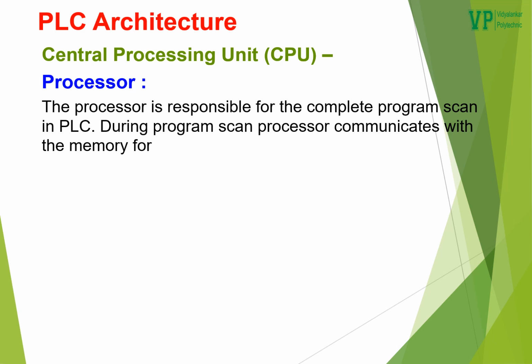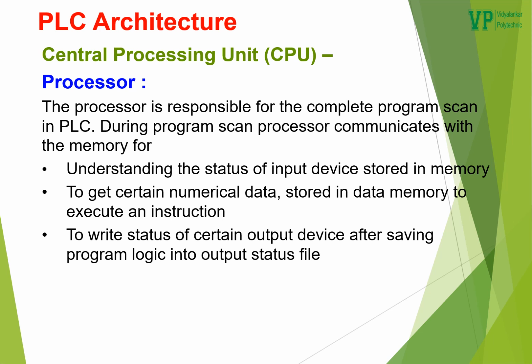The processor happens to be the brain of the PLC, as in the processor is responsible for the complete program scan in the PLC. During the program scan, the processor communicates with the memory for the following operations. First, understanding the status of input devices stored in memory. Then, to get certain numerical data stored in data memory to execute an instruction. And third, to write the status of certain output devices after saving program logic into the output status file.